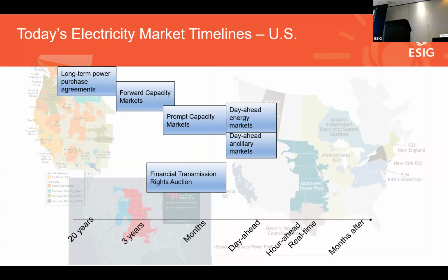When getting to day-ahead, most of the generation commitment decisions are made in the day-ahead market. So in most US ISO/RTOs, it's the energy and ancillary service co-optimization. So the market will clear all these products together, with a market clearing price. But really before that, a week ahead, most of the ISO/RTOs have a non-binding commitment process, really to make sure there's sufficient supply in the week ahead and also commit long lead generators if necessary.